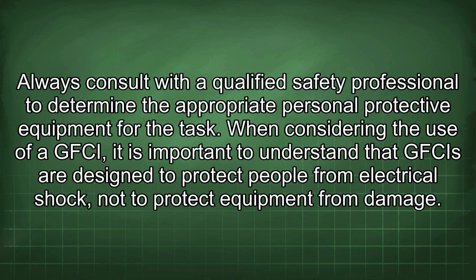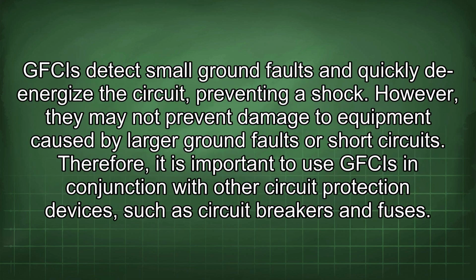When considering the use of a GFCI, it is important to understand that GFCIs are designed to protect people from electrical shock, not to protect equipment from damage. GFCIs detect small ground faults and quickly de-energize the circuit, preventing a shock. However, they may not prevent damage to equipment caused by larger ground faults or short circuits. Therefore, it is important to use GFCIs in conjunction with other circuit protection devices, such as circuit breakers and fuses.